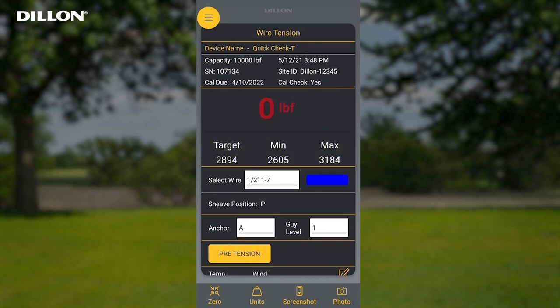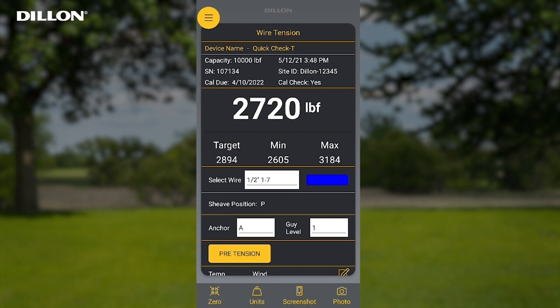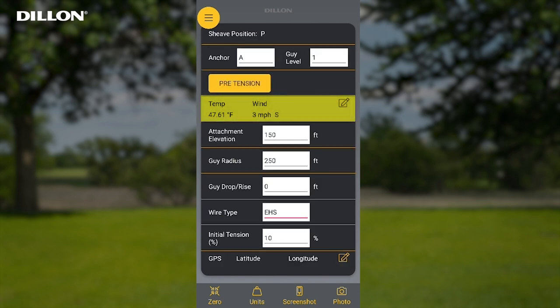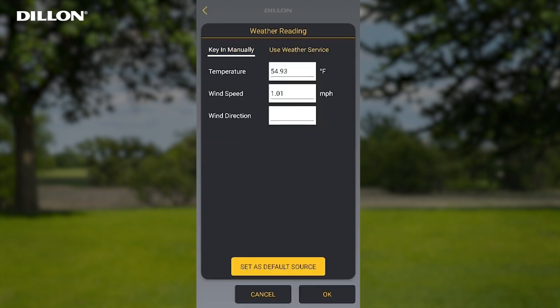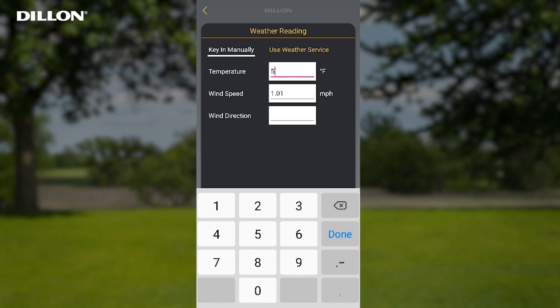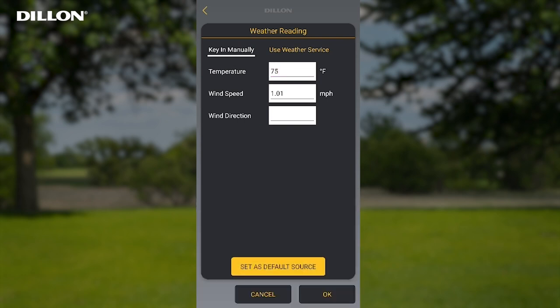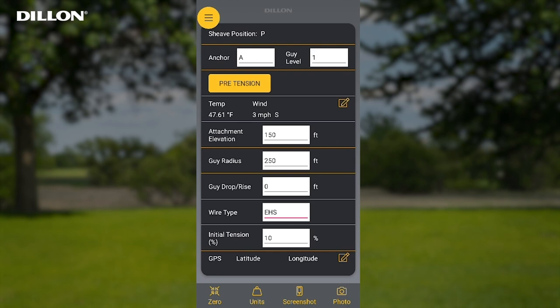The red live tension reading indicates the tension is outside the min and max values of the target tension. Once the wire is within the min and max values, the tension reading will be white. The temperature and wind speed are displayed on the wire tension screen and used to calculate the target min and max tension. By pressing the edit icon, you can change whether the temperature and wind speed are keyed in manually or updated automatically from the weather service. A data connection and location services are required for this option. Press OK when finished to return to the wire tension screen.